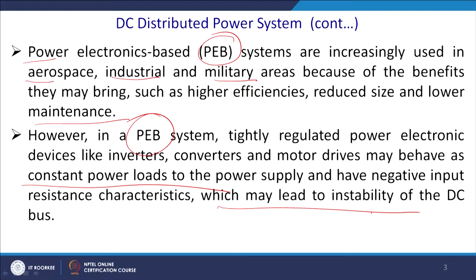However, in case of these electronics based systems, tightly regulated power electronics devices such as inverter, converter and the front end motor drive, AC to AC conversion, maybe in case of the AC microgrid, behave as a constant power load. Not only those DC CPLs, this also behaves as a constant power load to the power supply and has a negative input resistance. That is quite detrimental, which may lead to the instability of the DC bus. That is something we require to observe and find out the solution for, for healthy operation of the DC microgrid.